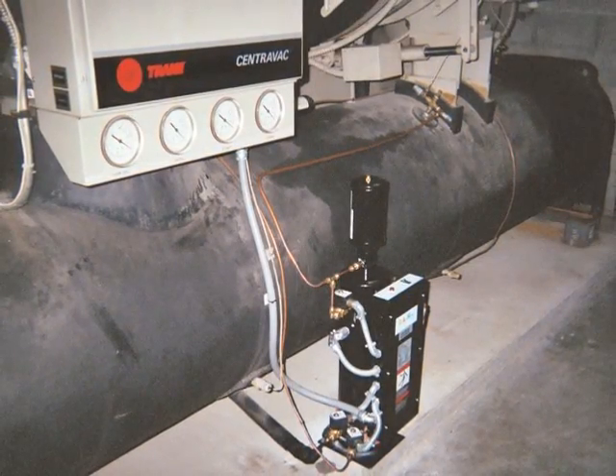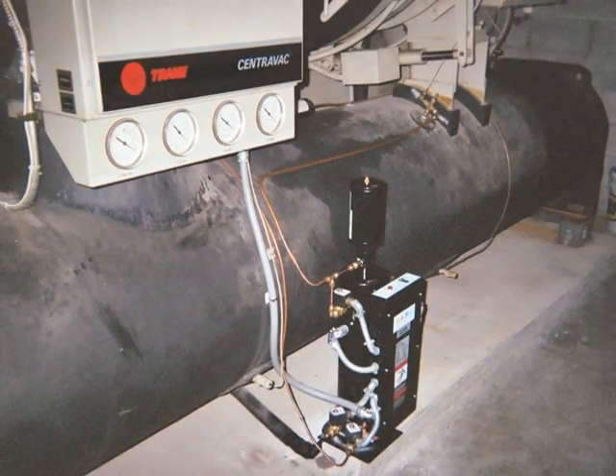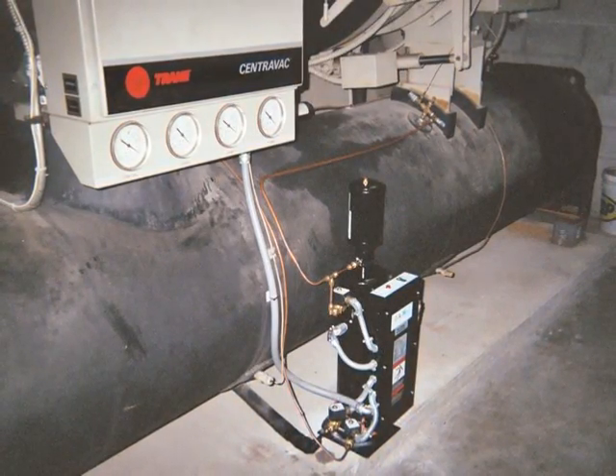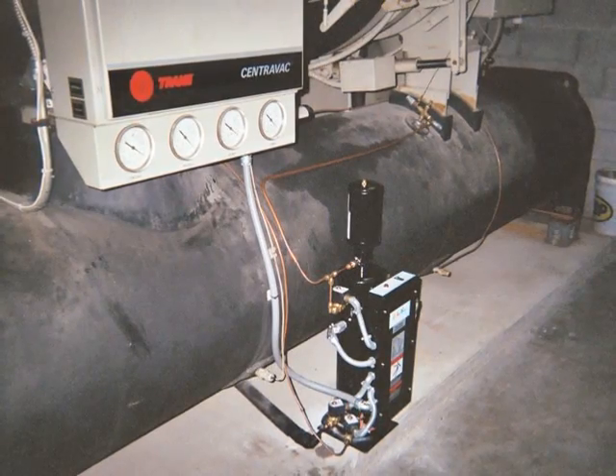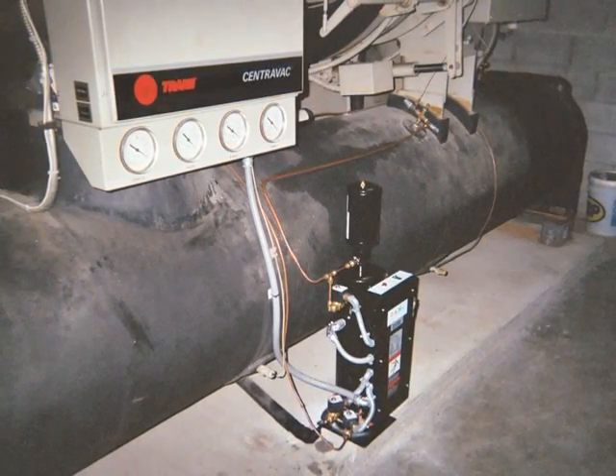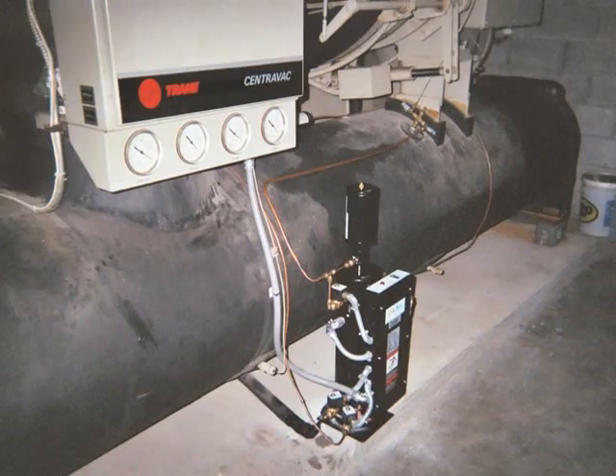Theoretically, a chiller operating at full capacity should have the least problem with oil migration because this is when the oil return system, or eductor pump, is operating at maximum efficiency. However, this is not the true case. You could even use an OAM purger on a type 1 chiller that runs at full capacity all year because oil migration continuously occurs, builds up in the evaporator. We've seen that these chillers typically float between 3 and 6% anyway, and the OAM will get you down to 0.5% oil entering in the refrigerant, thus saving a significant amount in energy saved.